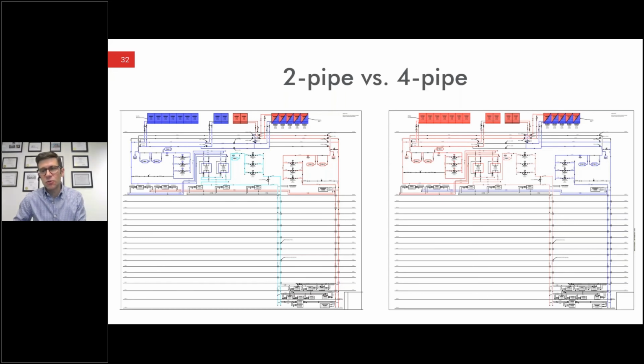The other thing to note here, and this was true for both buildings, is that we are providing the source side of the domestic water heating from what we're considering the 4-pipe loop that goes down to the amenity. In both conditions, that means the source side of our domestic water heating systems will go down as low as 40 degrees because we're providing 40-degree chilled water. So you do need to design your water-to-water heat pumps with a 40-degree incoming source load, something that these heat pumps can do. It's not a concern, but definitely make sure you're doing that. In the winter, those machines will actually be more efficient because they'll be provided with 120-degree water. So they are more efficient in the winter than they are in the summer. That's at the domestic load because those are off this 4-pipe system loop. And at NYU, they're off the 2-pipe, but the 2-pipe is in cooling in the summer. They also take some heat out of that loop and do a little bit of pre-cooling back to the air source heat pumps in the summertime. So you get a little bit of a simultaneous effect there. So just something to note.